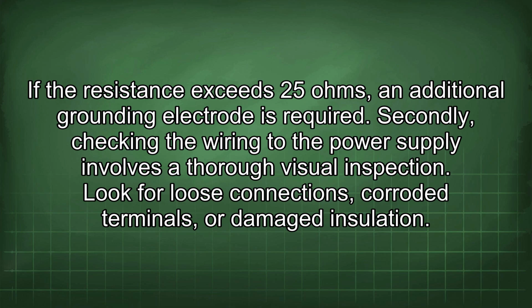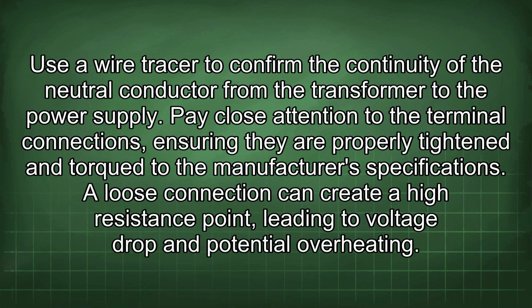Secondly, checking the wiring to the power supply involves a thorough visual inspection. Look for loose connections, corroded terminals, or damaged insulation. Use a wire tracer to confirm the continuity of the neutral conductor from the transformer to the power supply. Pay close attention to the terminal connections, ensuring they are properly tightened and torqued to the manufacturer's specifications. A loose connection can create a high resistance point, leading to voltage drop and potential overheating.